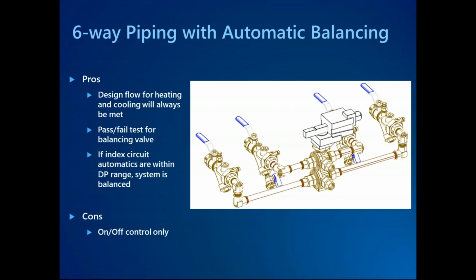If the differential pressure across both the automatic control valves is within the operating range specified by the manufacturer, that operating range is usually 2 to 50 psi, then not only is that index circuit working correctly, but the rest of the system is also balanced as well. So it's a lot easier to go through and verify performance of an automatic balancing valve paired with a six-way than some of the other solutions we've seen so far.